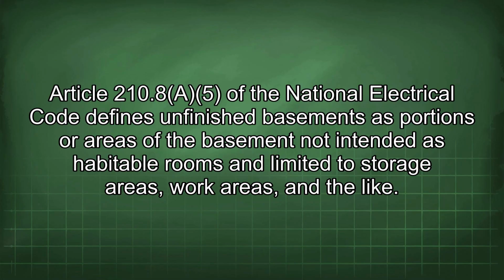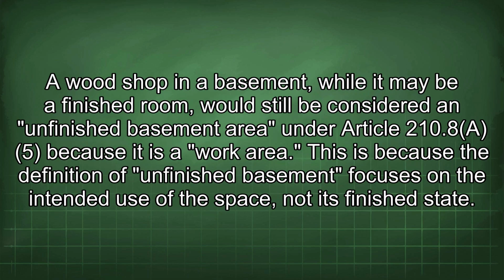Article 210.8(A)(5) of the National Electrical Code defines unfinished basements as portions or areas of the basement not intended as habitable rooms and limited to storage areas, work areas, and the like. A woodshop in a basement, while it may be a finished room, would still be considered an unfinished basement area under Article 210.8(A)(5) because it is a work area. This is because the definition of unfinished basement focuses on the intended use of the space, not its finished state.